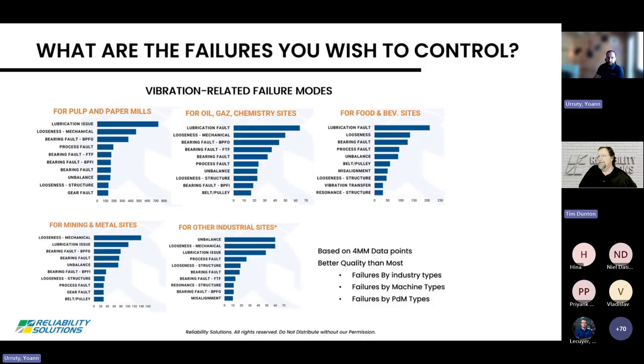Yeah, absolutely. They're all the same failure. What it's telling us, though, is we don't understand which of those it was. Exactly. So the bearing's loose. Are all the bearings you buy bad, with bad internal clearances, and they're all loose? Does SKF really do that bad a job?